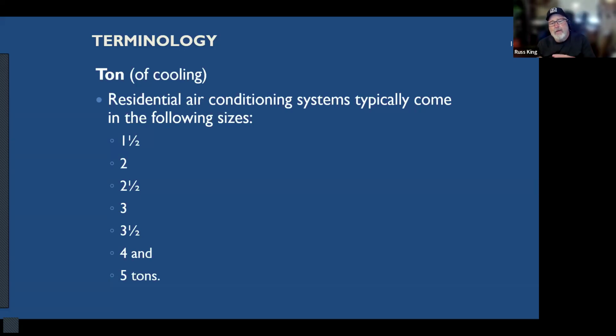All right. Now, this is before mini splits were super popular. Now that mini splits are super popular, they actually go down to half a ton. So you have half a ton, 3/4 ton, and 1 ton mini splits, and then 1.5, 2, 2.5, 3, and so on. And then another very interesting phenomenon nowadays: most heat pumps are variable capacity. A 3-ton variable capacity will act like a 3-ton, but it can modulate down to close to 2 tons.